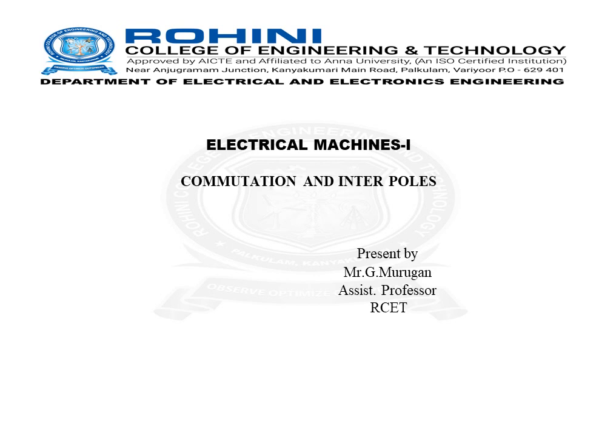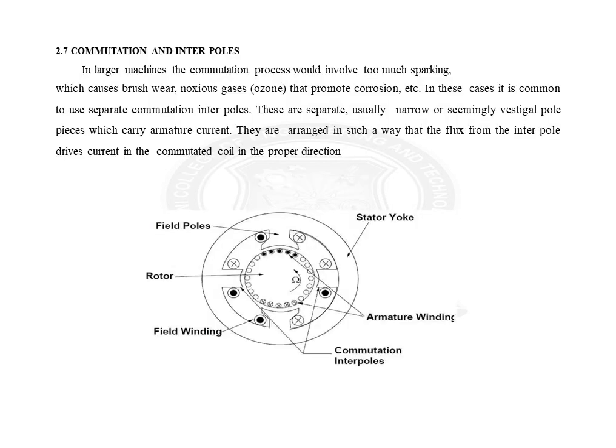Today we are going to see about commutation and the interpoles of the machine. In larger machines, the commutation process would involve too much sparking, which causes brush wear and noxious gases that promote corrosion. In this case, it is common to use separate commutation interpoles.